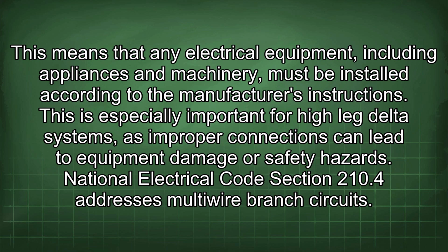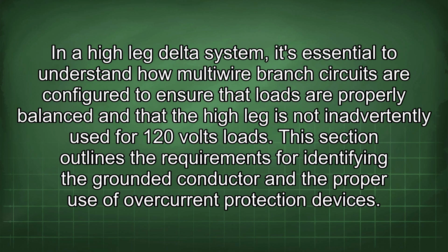National Electrical Code Section 210.4 addresses multi-wire branch circuits. In a high leg delta system, it's essential to understand how multi-wire branch circuits are configured to ensure that loads are properly balanced and that the high leg is not inadvertently used for 120 volts loads. This section outlines the requirements for identifying the grounded conductor and the proper use of overcurrent protection devices.